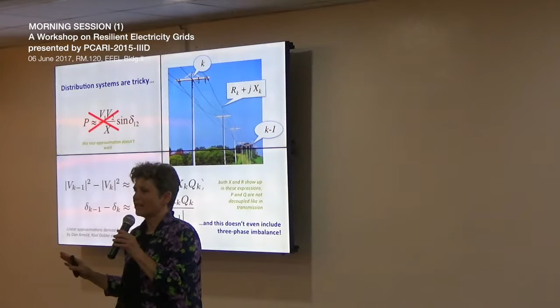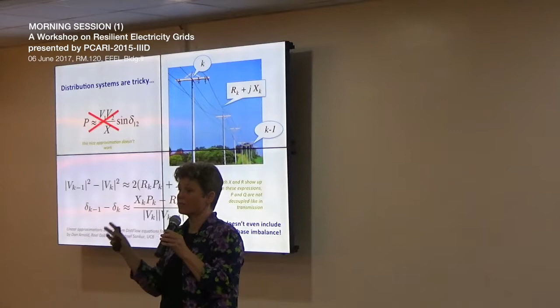Our team has worked on linear approximations that would relate voltage magnitude and phase angle on one hand to real and reactive power, P and Q, on the other hand, because we know we need a linear relationship to ever be able to run control systems, control algorithms. So we've come up with approximations that are probably pretty good a lot of the time, but they're much messier than what you see up there. You have to account for resistance and reactance at the same time, and real and reactive power at the same time. You can't decouple them like you can in transmission.